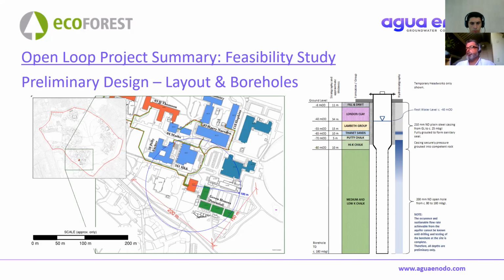I should mention that in the UK, generally we're not allowed to put water back in the ground at anything above 25 degrees C. So we have a restriction on the flow and a restriction on the delta T, and then we can start discussing with the engineers what's a reasonable thermal load we can sustainably supply with an open loop system.